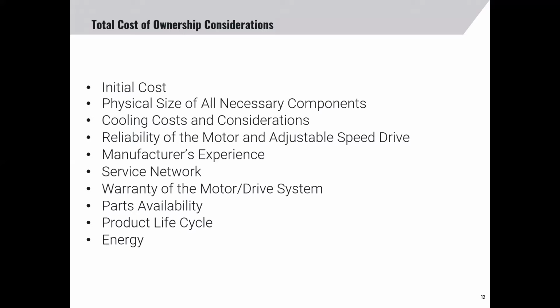For example, if you are purchasing adjustable speed drives, especially large medium voltage drives, what is the cost for the real estate where these will be installed? Oftentimes, these drives are installed in electrical houses or control rooms. A drive with a larger footprint will require additional costs for a larger building. You should also consider the cost for a cooling solution along with the monthly cost to operate that cooling solution. Many people don't realize it, but a typical 1,000 horsepower medium voltage drive requires the same cooling requirement as your average 2,500 square foot house. This requires not only a large upfront cost, but also monthly energy costs and yearly maintenance costs.